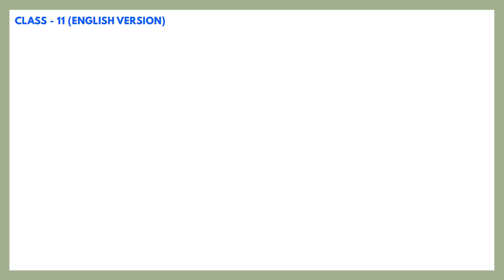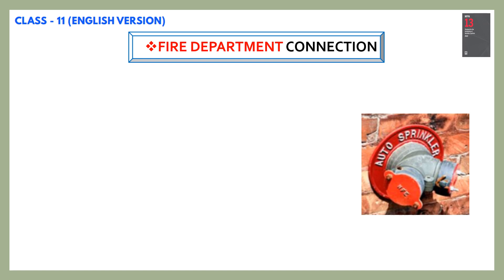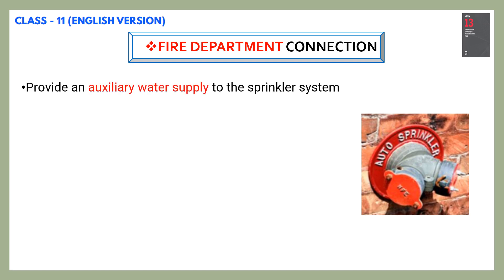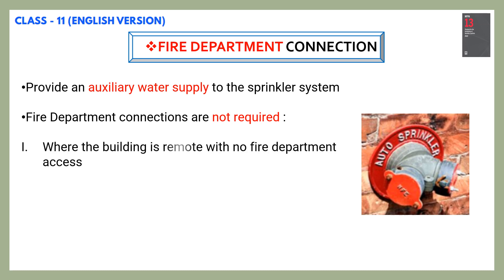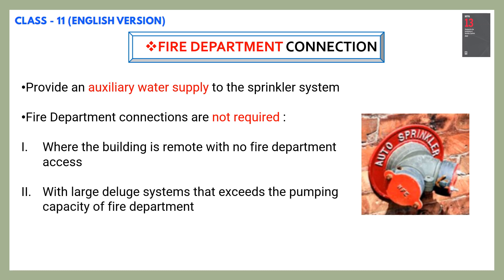We shall have a look at fire department connections. Fire department connections provide an auxiliary water supply to the sprinkler system. These connections are not required in special cases, such as if the building is in a remote area with no fire department access, or if there is a large deluge system that exceeds the pumping capacity of the fire department. Also, in a single-storey building not exceeding 185 square meters or 2,000 square feet, fire department connections — FDCs — are not required.